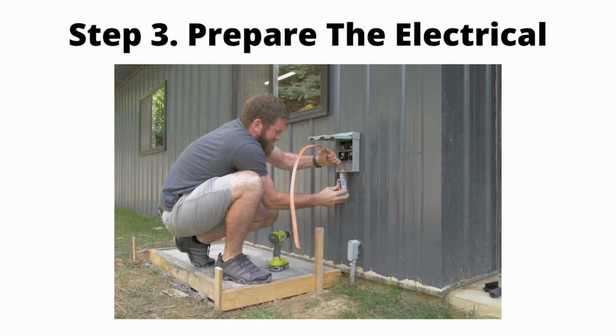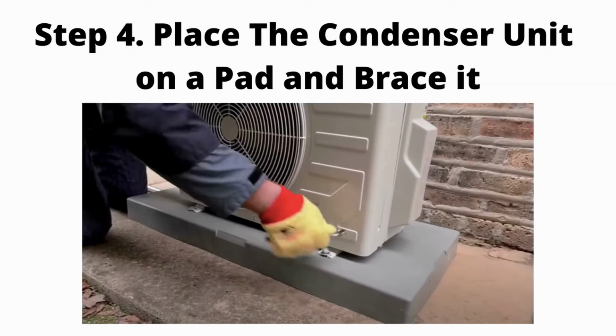If you have a 220-volt system, you will need to run the electrical from the main panel. The electrical wires will need to be inside an EMT conduit. We would not recommend doing this yourself unless you are an electrician. 220 volts can be very dangerous, so be careful. The fourth step is to place the condenser unit on the pad and brace it.